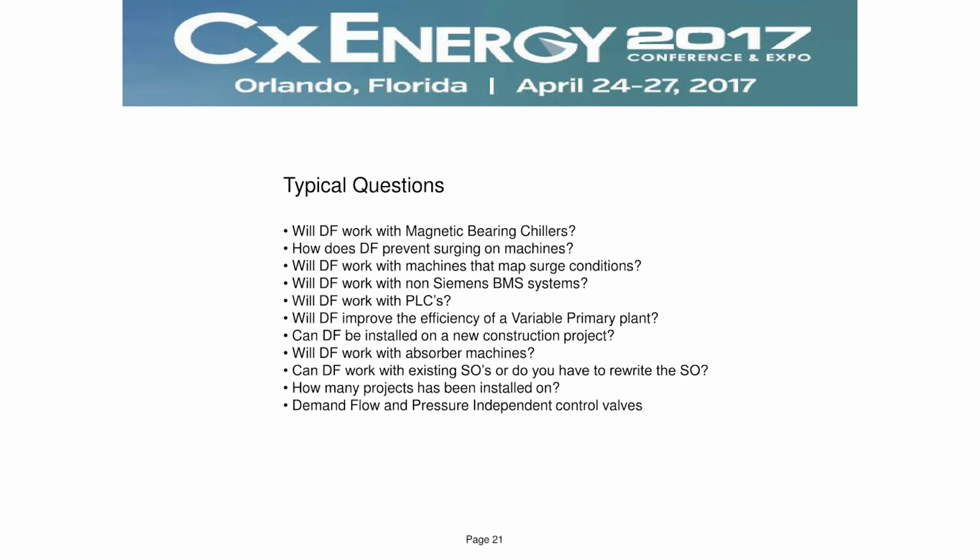So some typical questions that I have. These are ones that normally come. Will demand flow work with magnetic bearing chillers? Yes. We did a project not too long ago with McQuay, or Daikin, I should say, in which they supplied their magnetic bearing machines, and we had a demand flow project there. And we took their machine and improved the efficiency on that machine by about 35% over its rated efficiency for the year. When you think about what makes a magnetic bearing machine so efficient, it has nothing to do with the flow of water through the machines, right? It's all bearing related. So definitely it works.